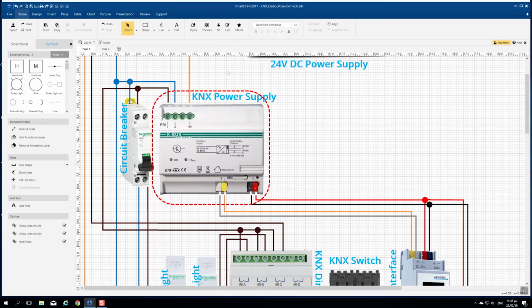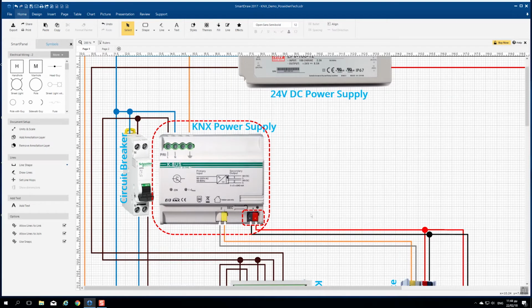One KNX power supply, this is from KBus. Here, we will connect line and neutral from the circuit breaker and earth from the plug. The KNX power supply will generate the 29 volts required by the KNX bus. So, red and black cables are the KNX bus that will provide the KNX devices not only the voltage in order to operate, but also the path for the telegrams that will carry commands and feedbacks among all KNX devices.